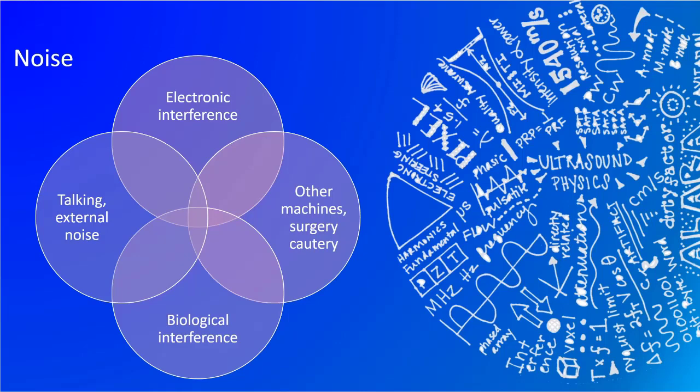As an example of noise that I have experienced, when I went up to the ICU to scan a patient, some of the machinery in the ICU is at the same wavelength and interacts very oddly with our transducer, with our machine. And so you can see these extra reflectors that don't belong there. And it only happened with this one transducer, so if we changed transducers, we got rid of those extra external noise sources.